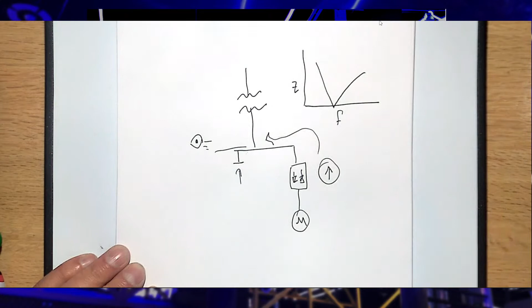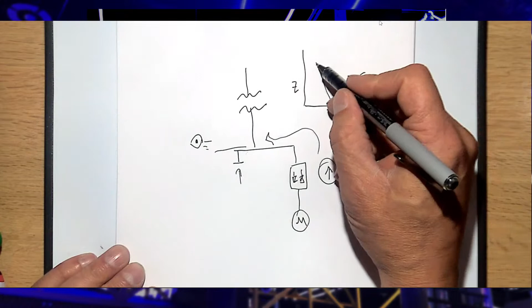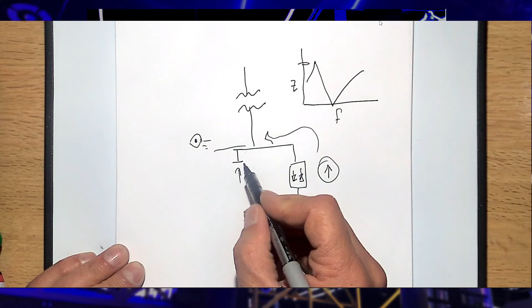But if I put a capacitor here, what have I done? I've given this current another path to go into. And if I look at a graphic of impedance, looking into this bus, I could have a low point for that impedance. If this is impedance and this is frequency, at some frequency, it's going to look like a sink, like a harmonic filter essentially. But the problem is it's also going to look like a high impedance here. And that's because this capacitor and this inductor, which is a transformer, are essentially in parallel.